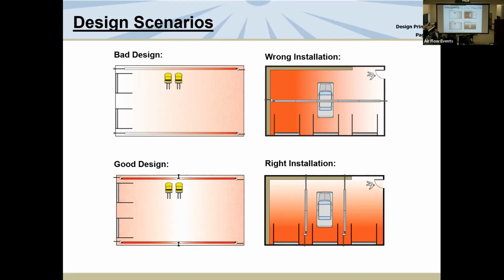The other thing that we see a lot of in firehouses, ambulance bays, trucks for garbage, these city buses, is people like to run the heater directly across the bays. And that's a hazard because often those trucks are quite tall. And also it doesn't allow the infrared heat to get down to the floor. So to stay out of trouble, put it between the bays and run it parallel to the bays. Okay? These concepts are what our design book touches on, as well as the videos. Each one of the chapters of that design book is on YouTube. So you could go to YouTube and watch any one of these videos on design. It's a 4-minute clip. So you can watch our whole book in about half an hour. There's 7 chapters reading. It's worth doing so.